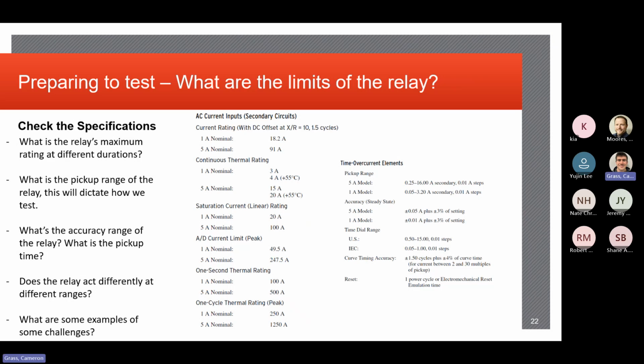Understand the parameters of which currents or voltages necessarily need to be picked up at what time and in what zone, et cetera. But understanding the absolute limits that the relay can handle, or that it should be monitoring during a fault scenario, in the aspects that you'll be testing, you've got to understand those as well to make sure that you don't exceed those at any point, because some of those might get a little skewy, especially in certain situations.